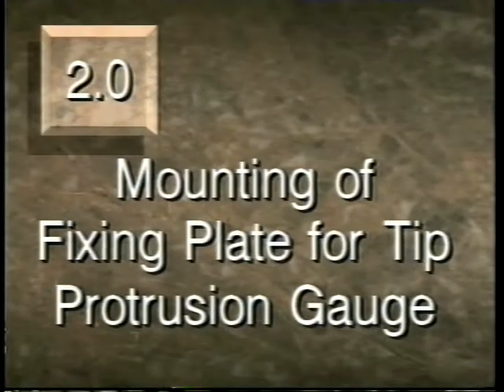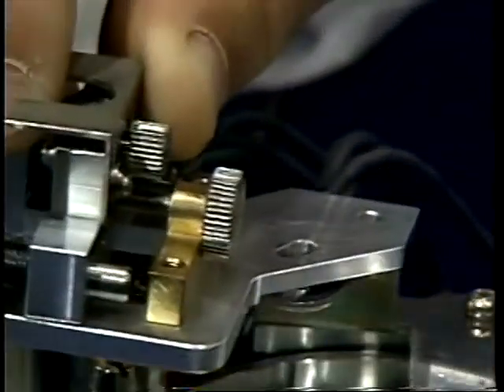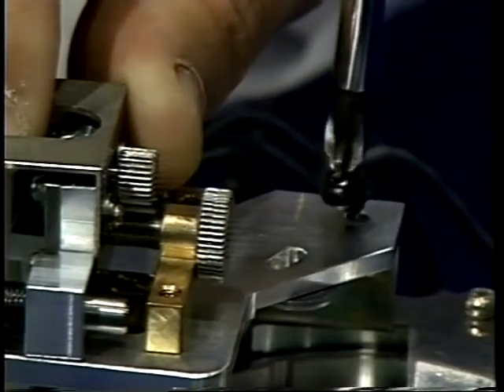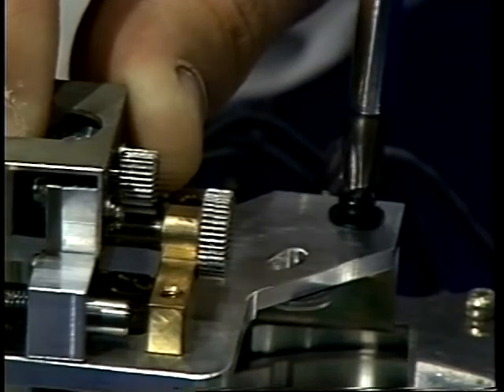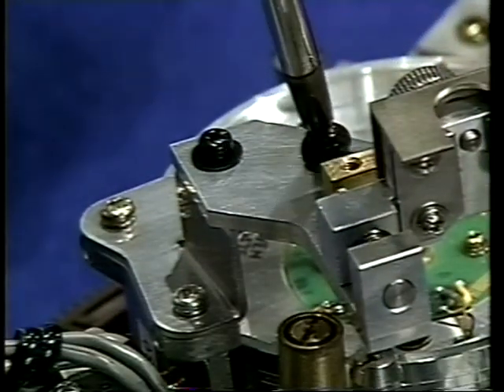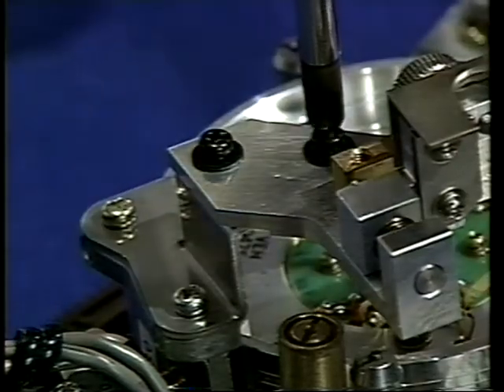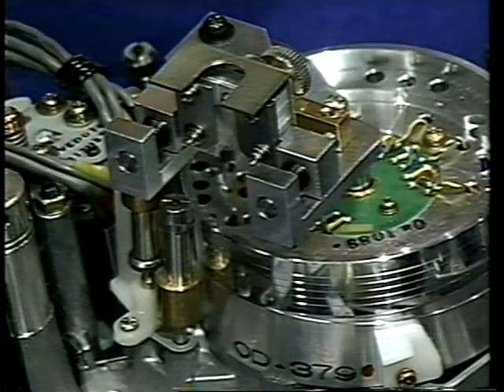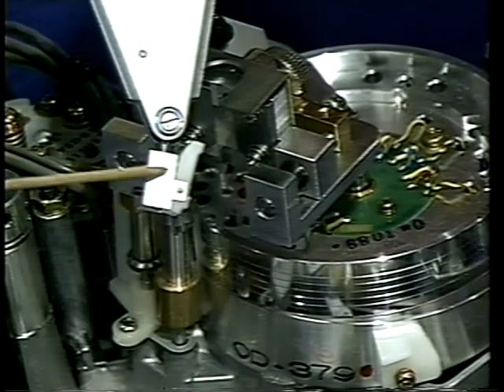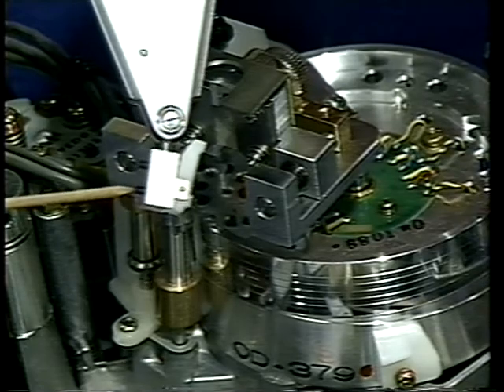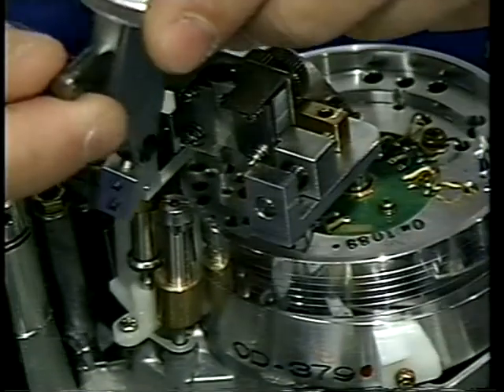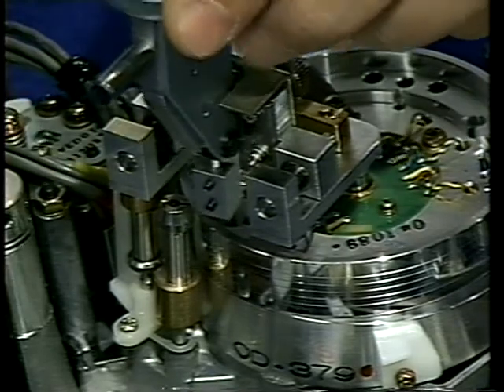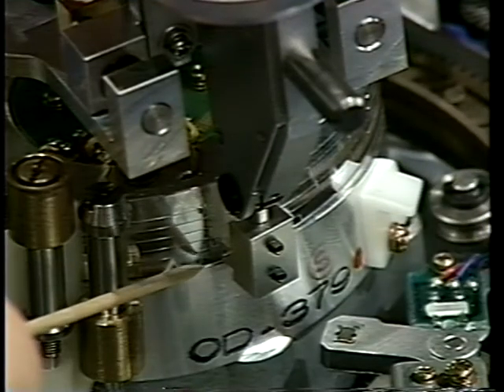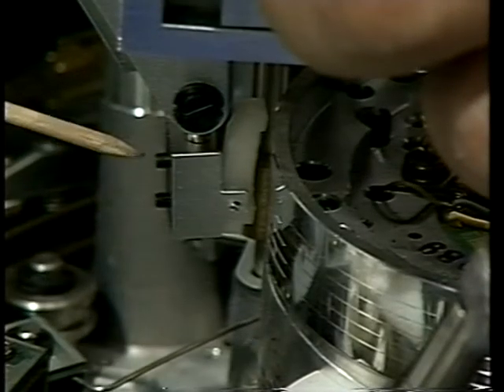Mounting of the fixing plate for the tip protrusion gauge. The fixing plate for the tip protrusion gauge is mounted here and attached with screws. Now the gauge can be attached. Make sure that this part at the bottom is in a straight line, in the same plane. Then insert it down here. Make sure that the base does not touch the lower drum, and make sure the top of this part is even with the top of the upper drum.